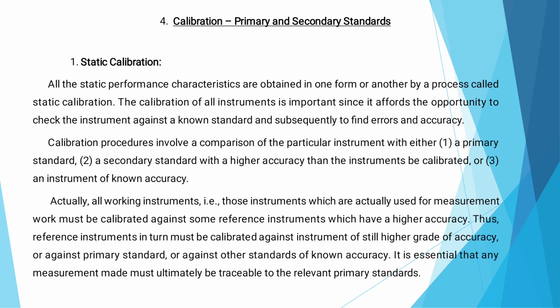And even in the case of secondary standards, we will observe the standards serving the basic reference standards, where the industrial and commercial measurement laboratory is used. So the individual industry is responsible for maintaining and checking these standards locally against regional references. Periodically, these secondary standards are sent back to the national standard laboratories, and they are returned to the industry with an official certification verifying their exact measured values.